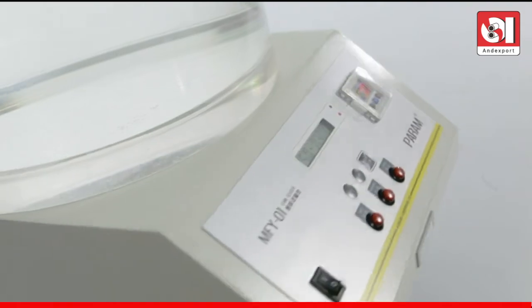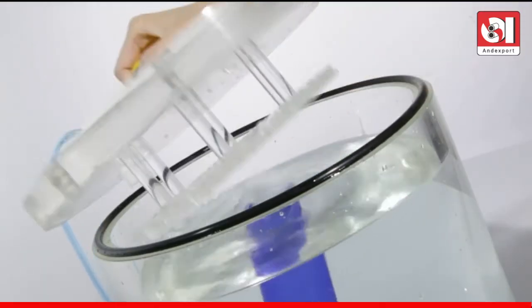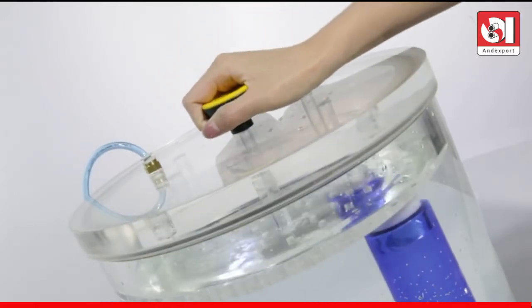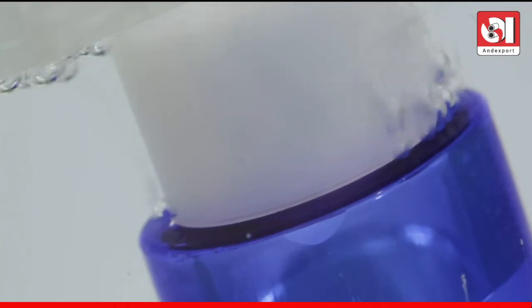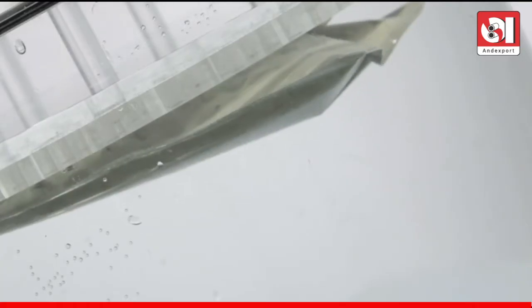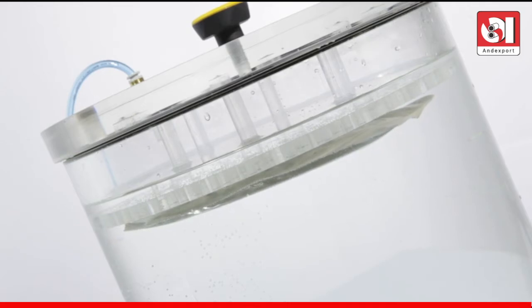MFY-01 works by creating a vacuum in the test chamber to create a pressure difference between the inside and the outside of the specimen.